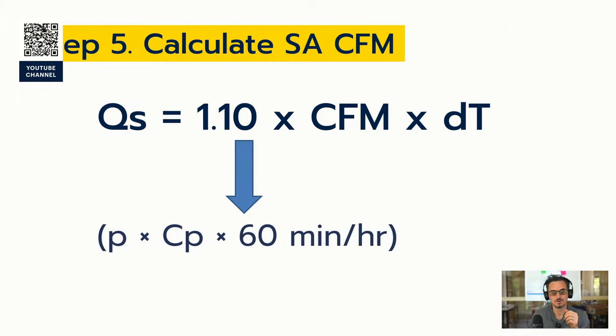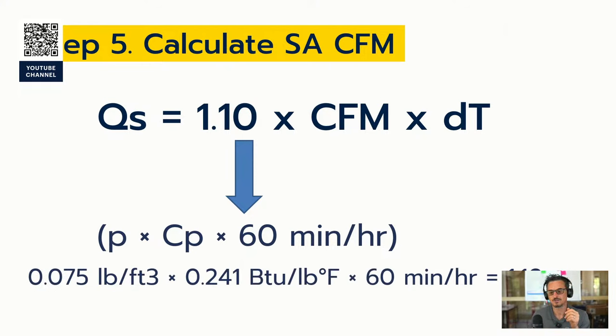All right, so what is this 1.1? If you're older like me, it was always 1.085. As a matter of fact, it was 1.085 on this presentation until this morning, because I've given it so many times and people come up to me and say, it's 1.1 now. Okay, I get it. So now I'm getting into the new era and I've changed it to 1.1. What this is, it's not a constant. It's the density times a specific heat times a conversion factor of 60. That's how this is calculated. And it is at standard air conditions, which I understand is 69 degrees and sea level.